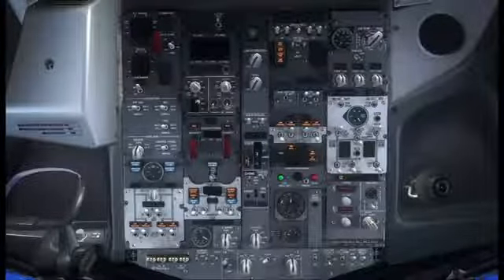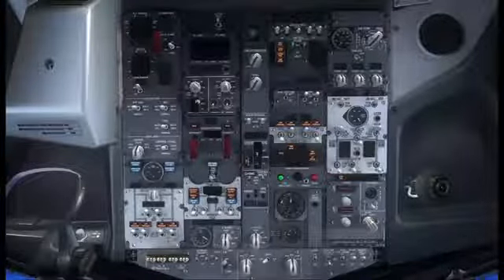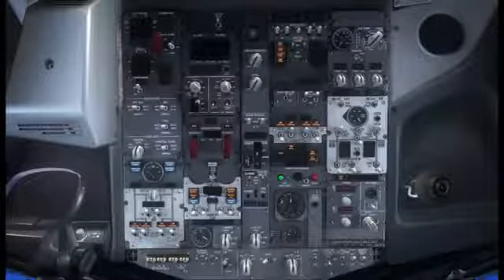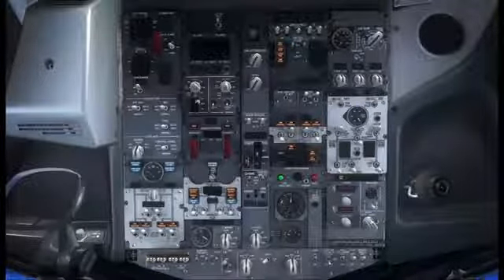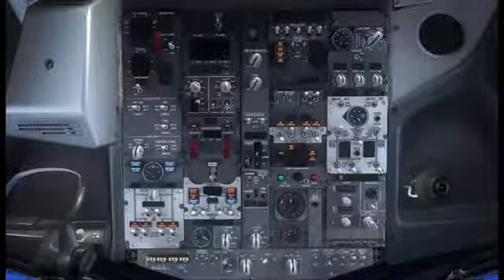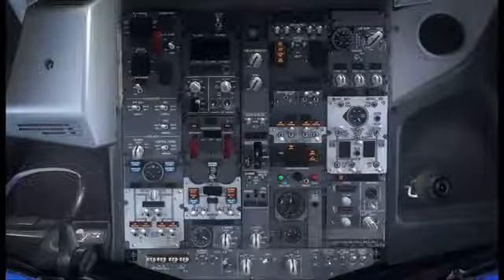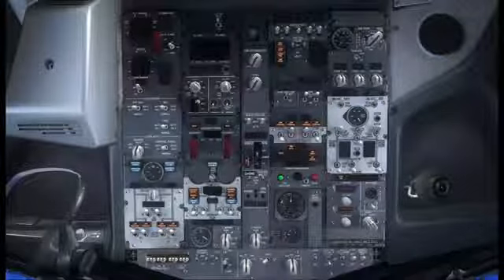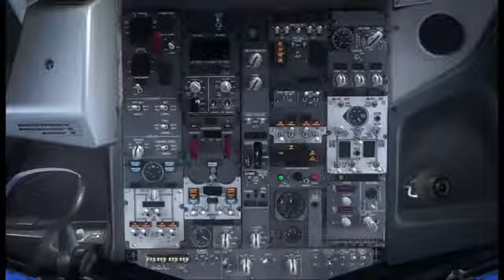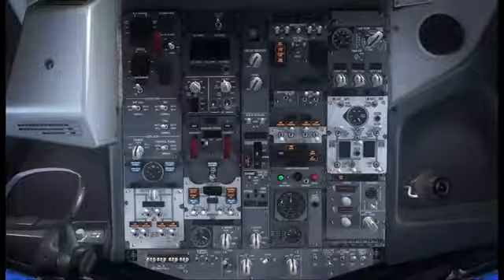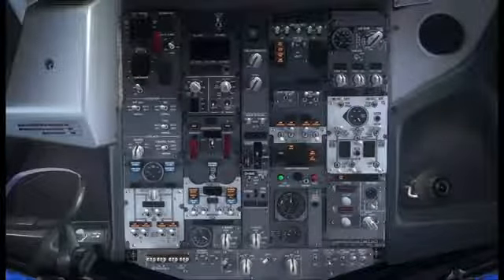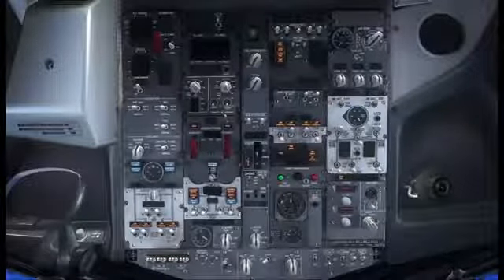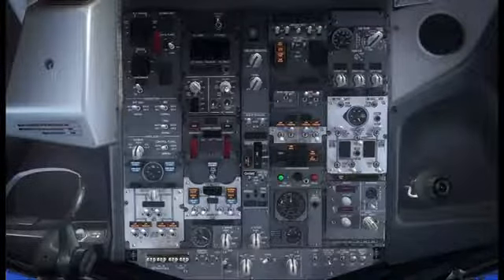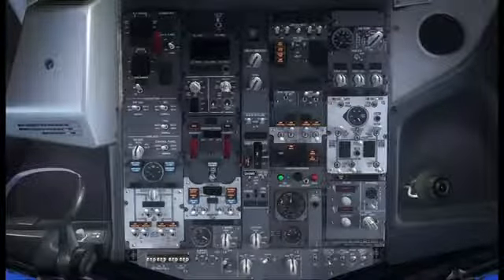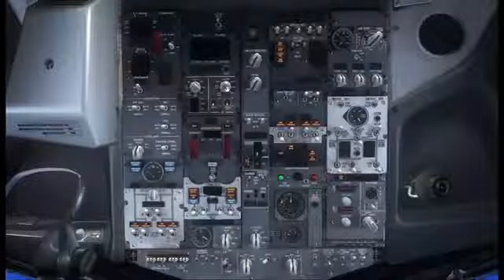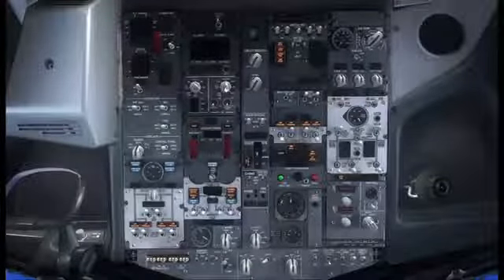Switching on the battery will energize the battery bus, switched battery bus, DC standby bus, the static inverter, and thus the AC standby bus. Note that if the standby power switch is not in the auto position, only the battery bus and switched hot battery bus will be powered. This is not to be confused with the hot battery bus, which remains powered regardless of switch position, to allow power to essential systems such as fire suppression at all times.